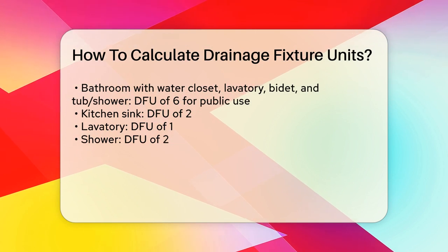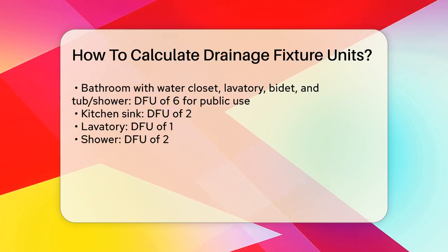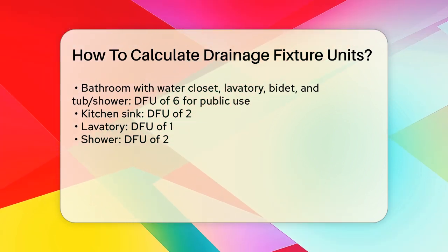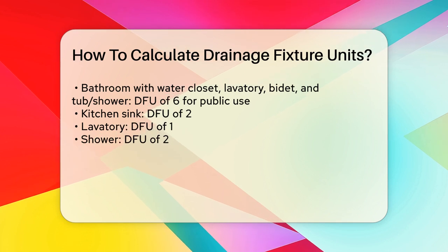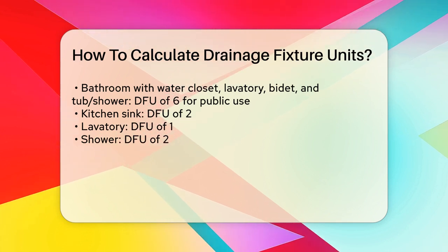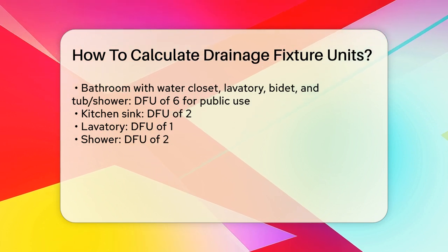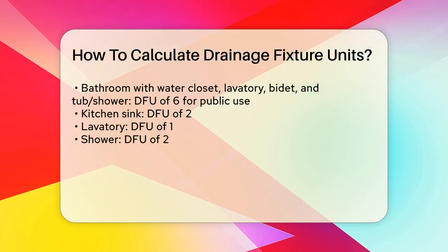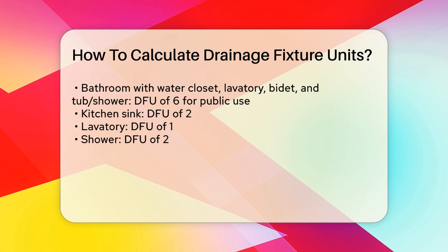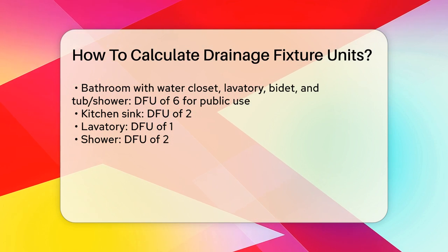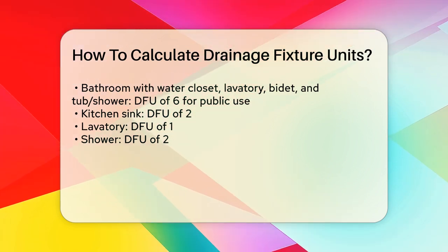Here are some specific values to keep in mind. A kitchen sink typically has a DFU of two. A lavatory usually has a DFU of one. A shower is generally assigned a DFU of two. A water closet can have a DFU of three or four, depending on the type and installation.